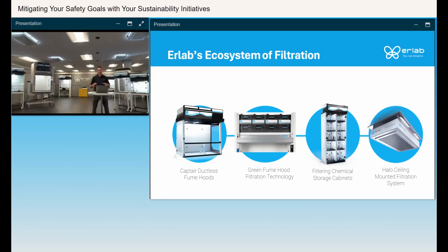And then we've also taken that filtration technology from our ductless fume hoods and put it on where you store your chemicals in our filtering chemical storage cabinets. When you store chemicals, open bottles, samples, satellite hazardous waste accumulation containers in a closed cabinet that's not ventilated, the concentration of the vapors builds up. And when you open that up, you breathe it in. I'm sure most of you know when you open one of those closed cabinets, and it smells. So those odors you're smelling are chemical vapors. They're not good to breathe in, especially at that concentration. So our filtering chemical storage cabinets constantly filter the air within those cabinets, capturing any chemical vapors that are released.